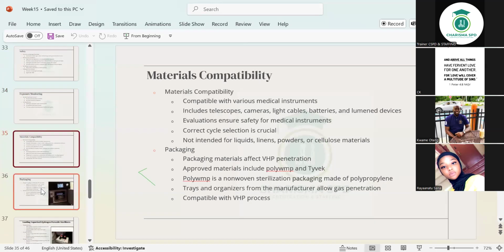Material compatibility. Compatible with various medical instruments, including telescopes, cameras, light cables, batteries, and lumen devices. Evaluations ensure safety because they always have to evaluate this machine. How often? That's why we document everything. How often is it failing? How often is it passing? How many instruments is it taking in capacity? You have to take all that into consideration.